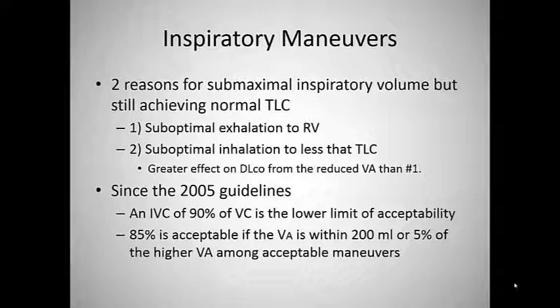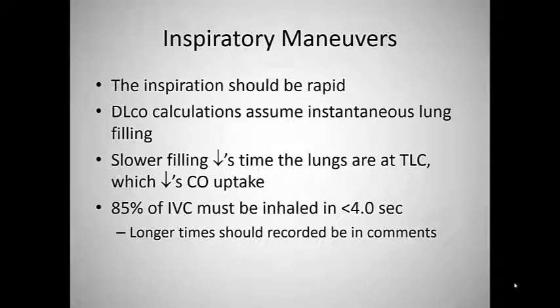I said that incorrectly. In 2005, they said 85% was the acceptable range. You had to have an IVC at least 85% of your forced vital capacity, be a quality one. Well, they changed the standard on us again. They went back to 90% again, with a couple caveats on there that I'm going to show you.